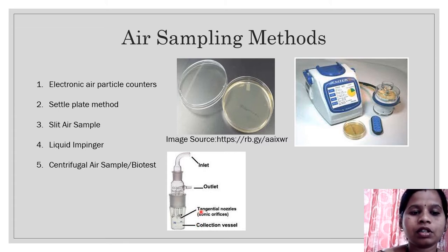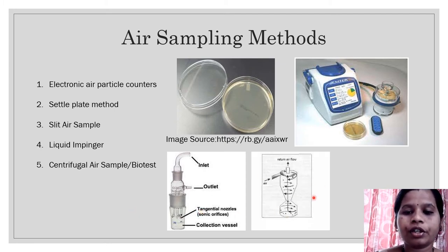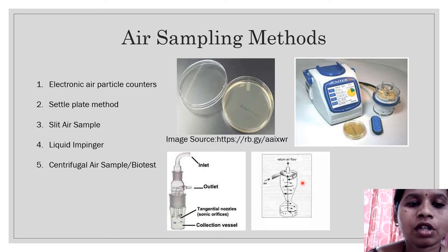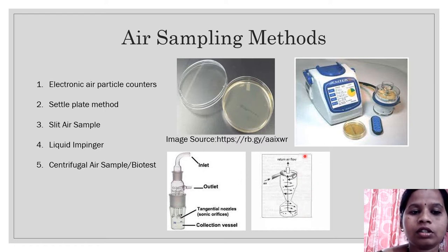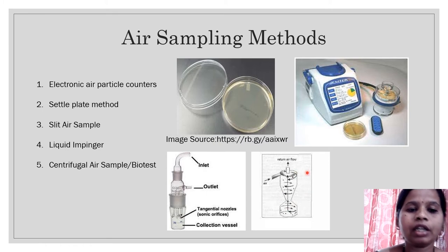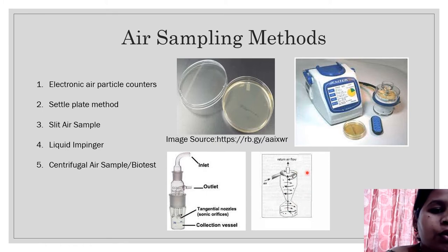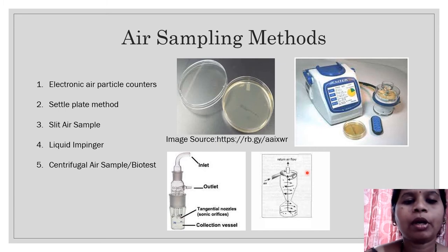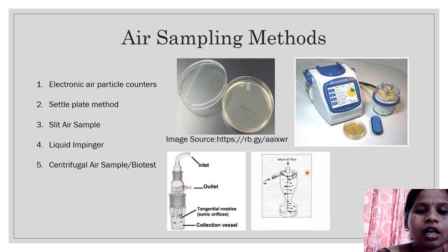Next is the centrifugal air sampler. Airborne microorganisms approximately 6 inches above the sterile area are checked. The air is passed through and centrifuged at approximately 4200 RPM, and the microbial particles are impacted at high velocity onto the incubation medium. The counting of microorganisms is then performed.